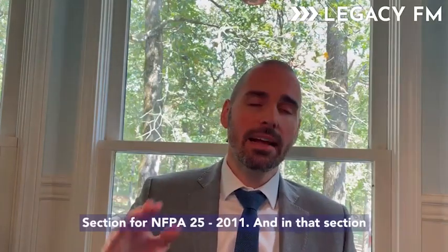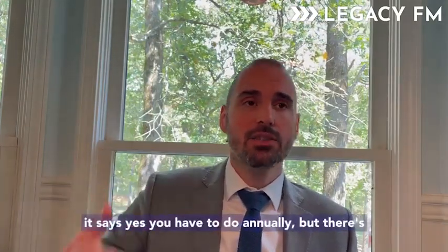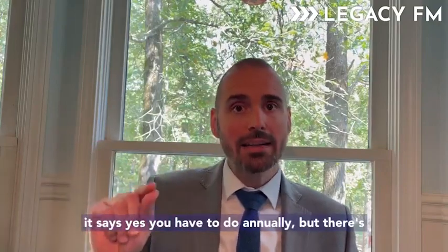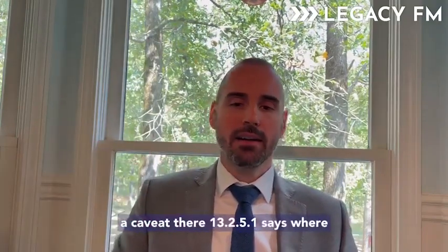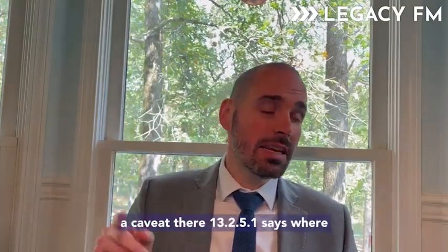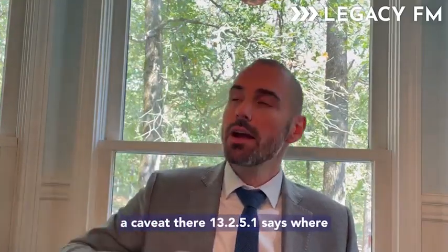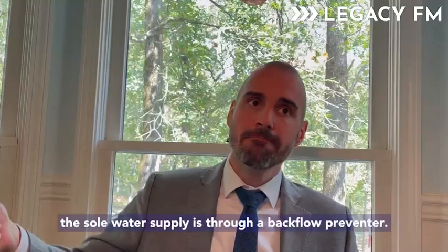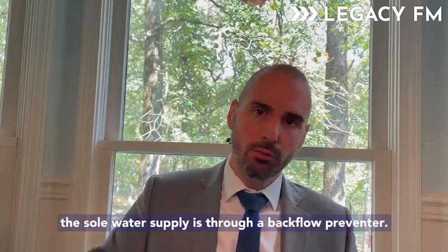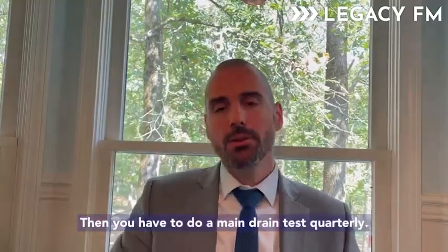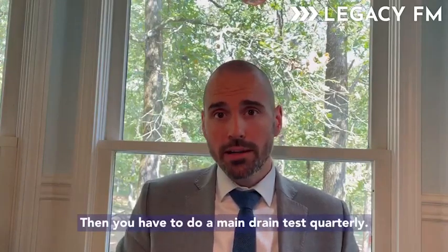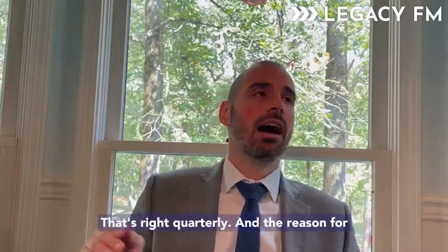And in that section, it says, yes, you have to do it annually, but there's a caveat there. 13.2.5.1 says where the sole water supply is through a backflow preventer, then you have to do a main drain test quarterly. That's right, quarterly.